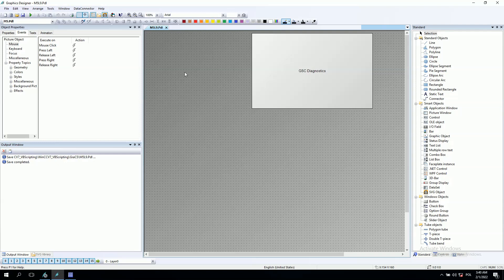It's a pop-up and the operator doesn't see this. All scripting are frozen, so if you have 1000 scripting and the message box appears on your background of your SCADA runtime, all functions are stopped, are frozen.